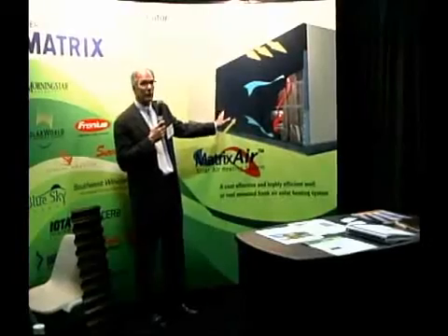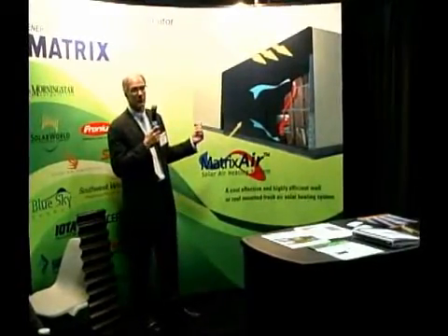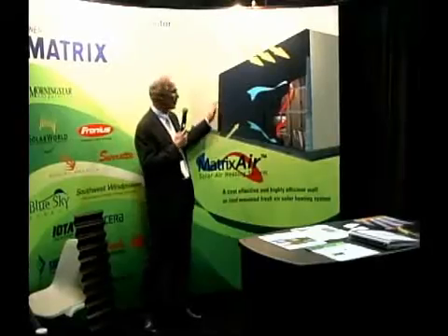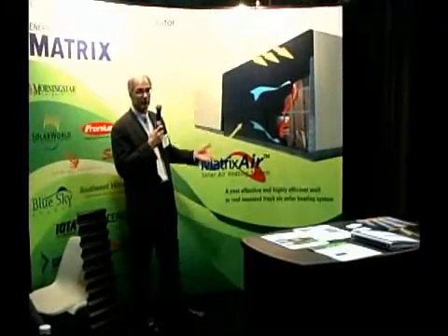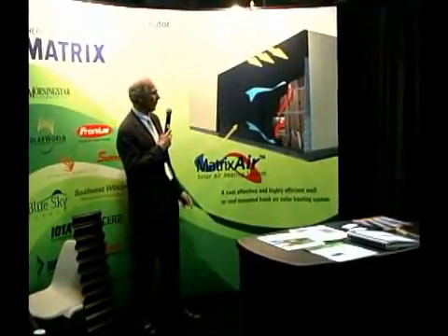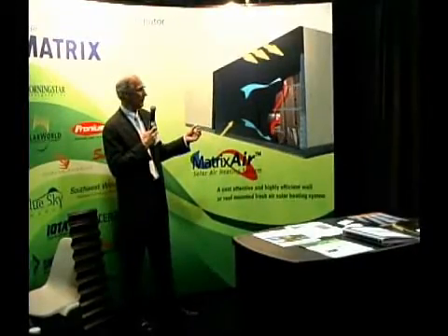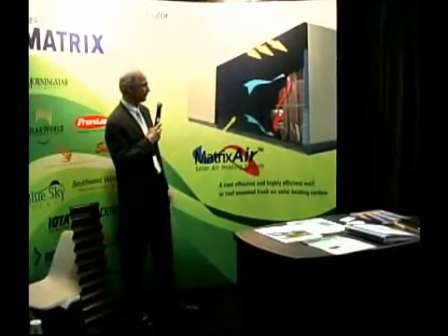Other applications include crop drying — any drying application for produce, be it corn, tobacco. In hot climates, we use it for drying tea, or drying nets in California. In those cases, we can modulate the amount of air going through each square foot of the collector. By doing so, we raise or lower the temperature. We're still always getting the 700 watts per square meter of energy; however, we are alternating the flow rate and the temperature rise of the air. As a result, we can vary the temperature and air volume according to the drying process of the produce being dried.